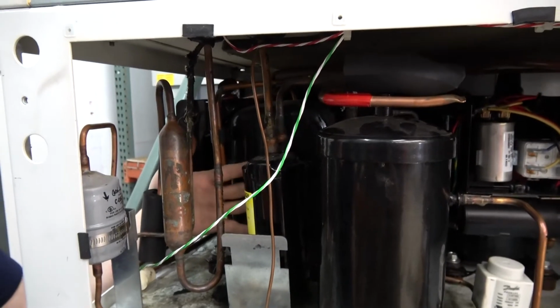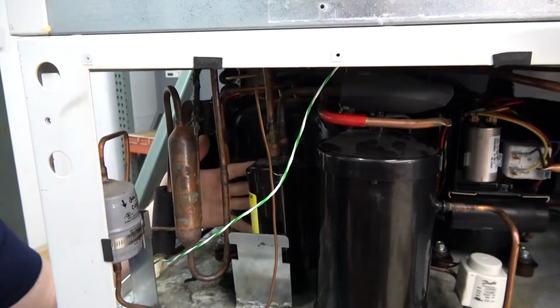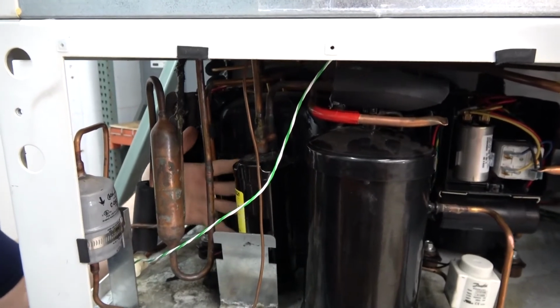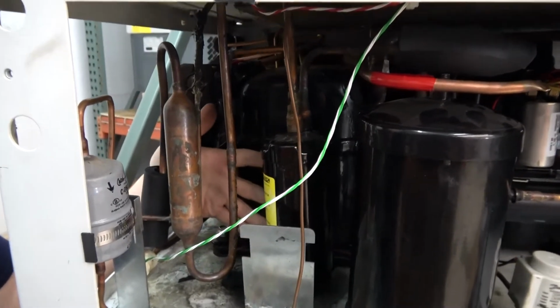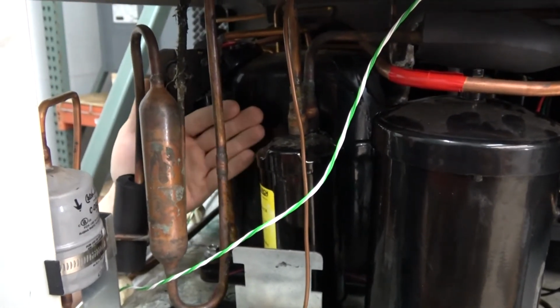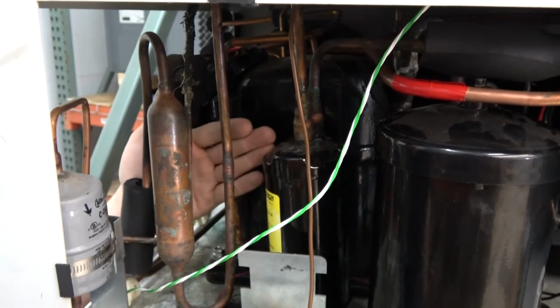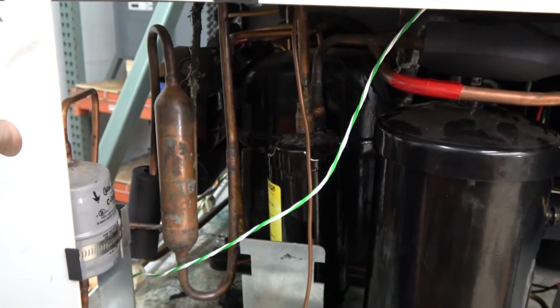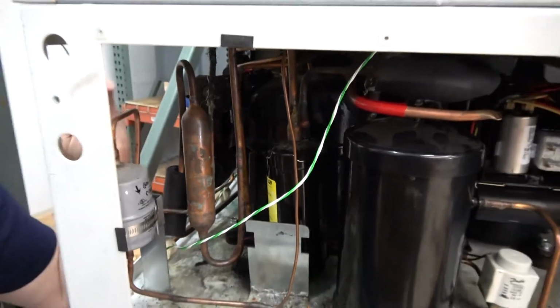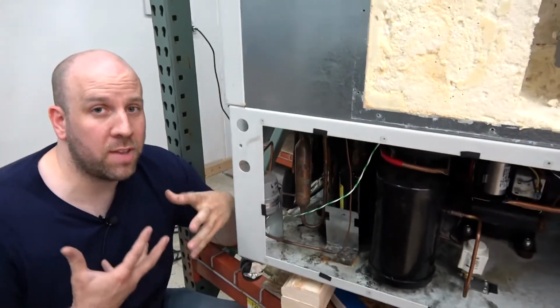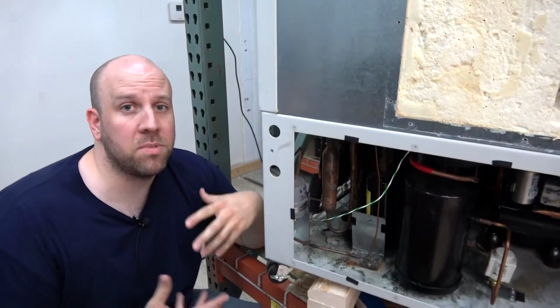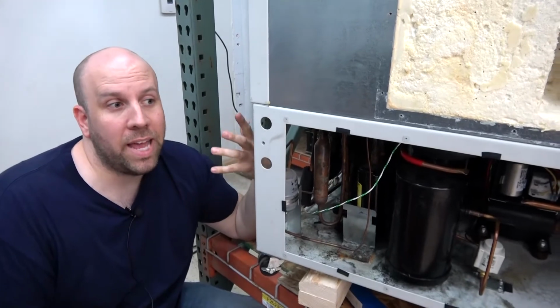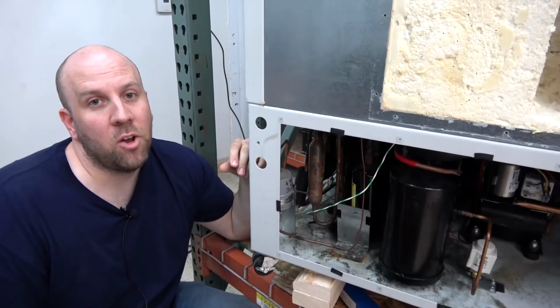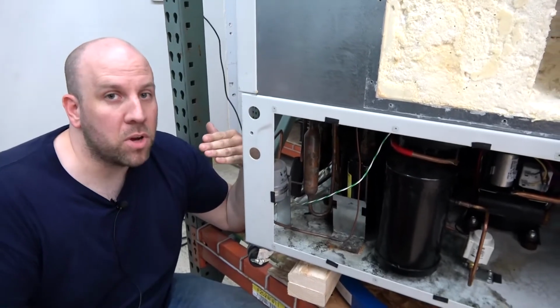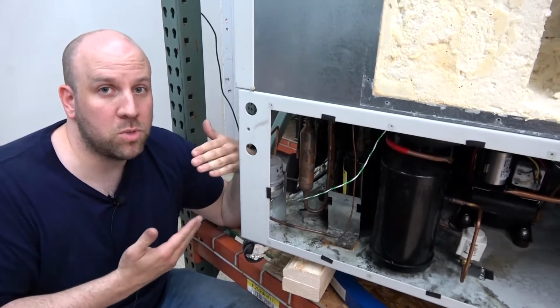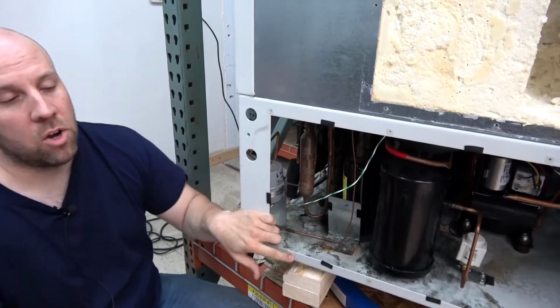The accumulator is a way of storing excess refrigerant, especially liquid. So this is a way of increasing some of the capacity of the refrigeration system, and it's very important for preventing liquid refrigerant from getting back into the compressor. Because if liquid refrigerant gets into the compressor, it can destroy the compressor. A lot of these have a safety where if liquid does get in, the compressor will have a harder time compressing, and it'll draw more amps, and it'll actually cut the compressor out because it has basically an overload protection built into it. But it'll come right back on once that overload switch cools off, and it'll just keep doing it. So it will eventually hurt your compressor or destroy it.